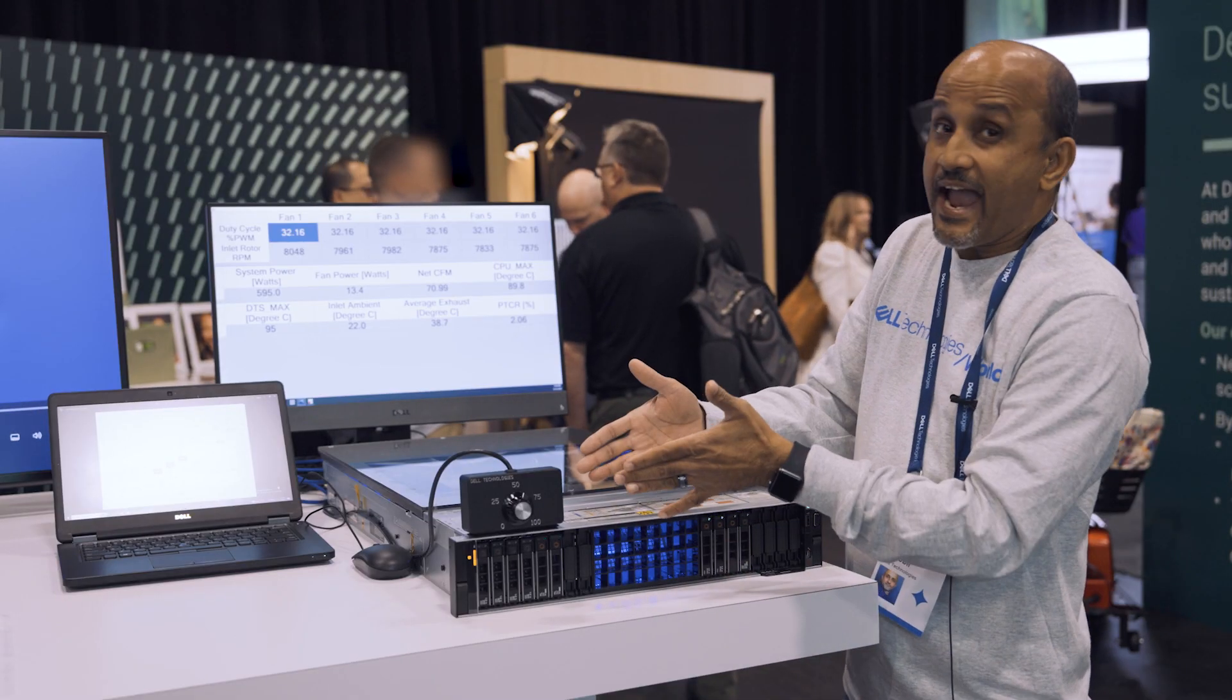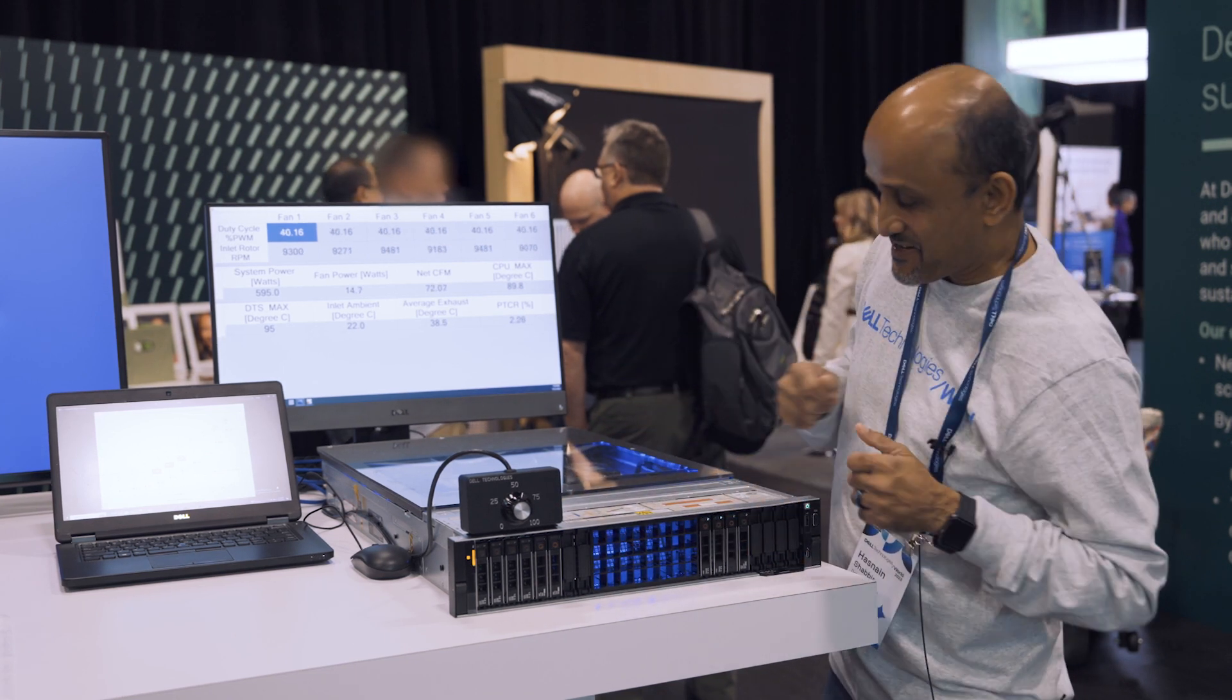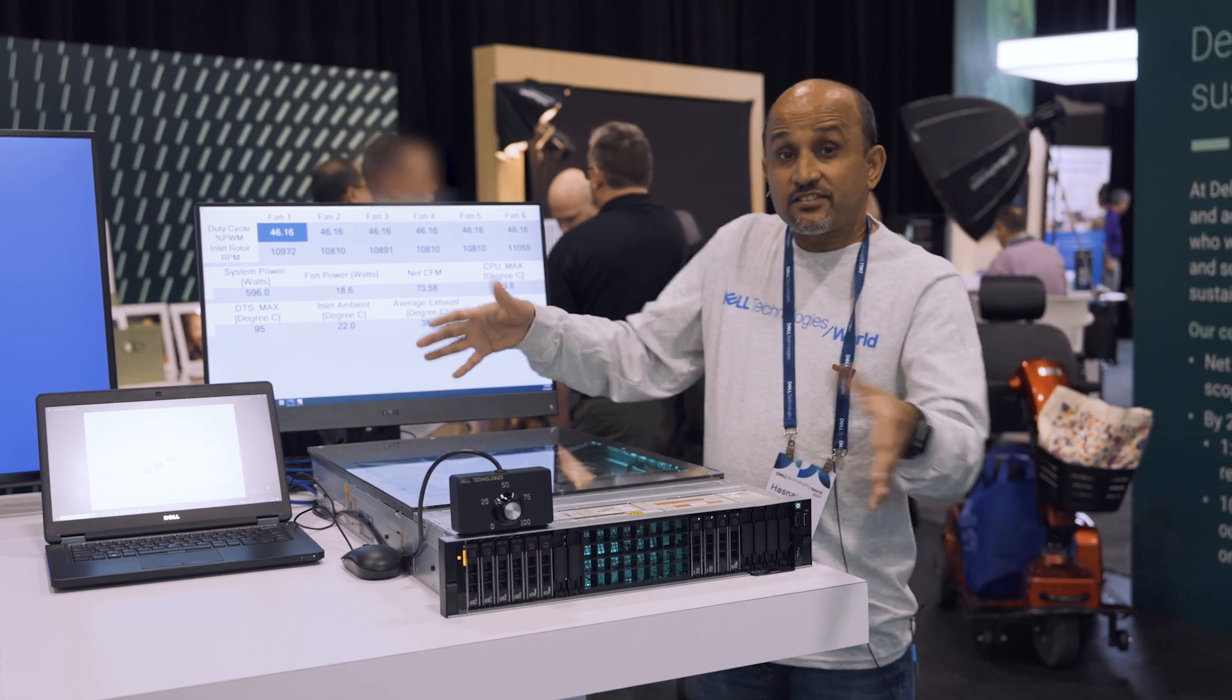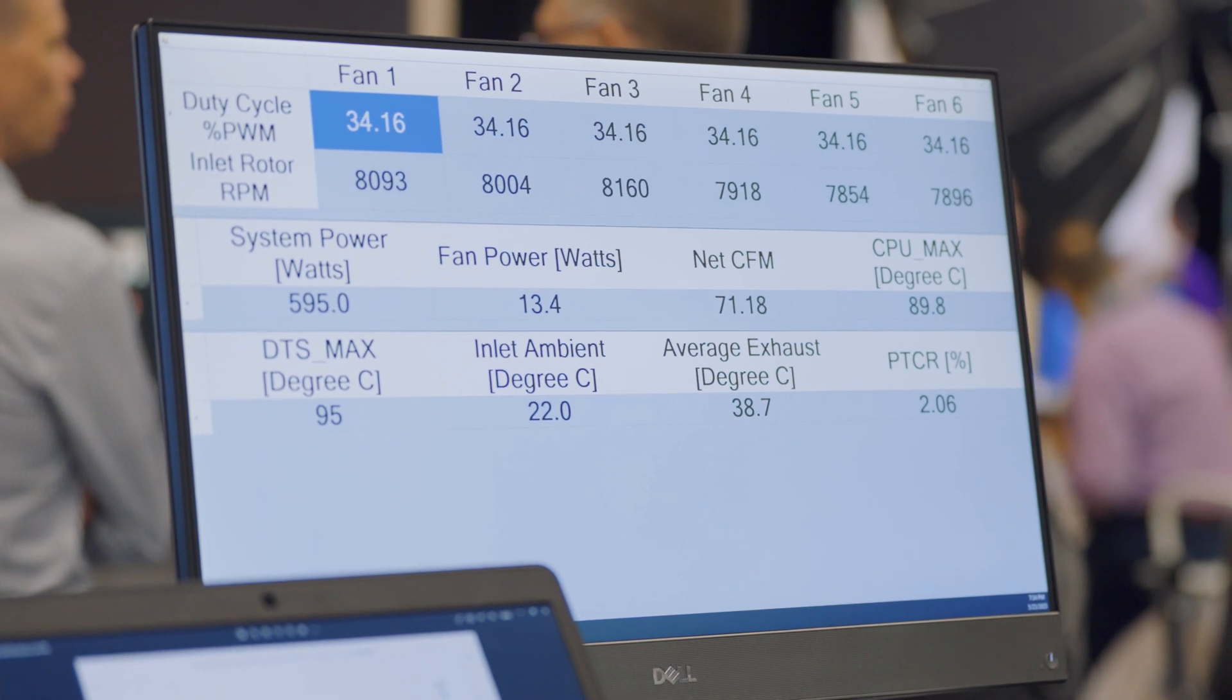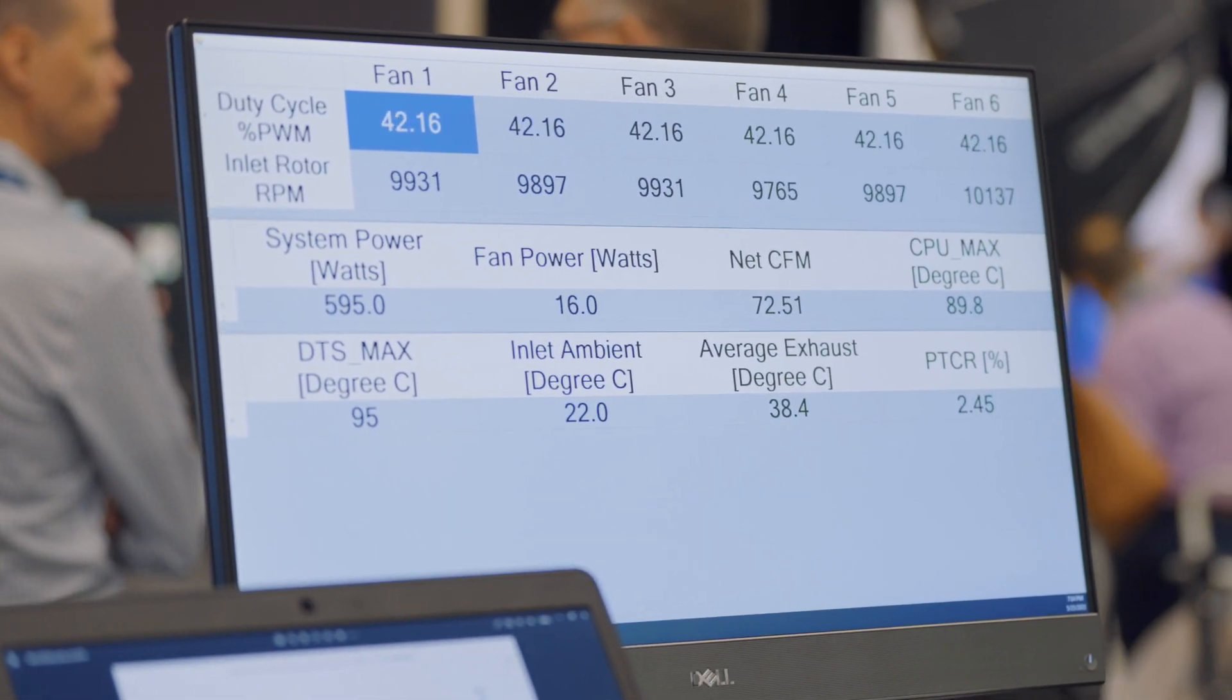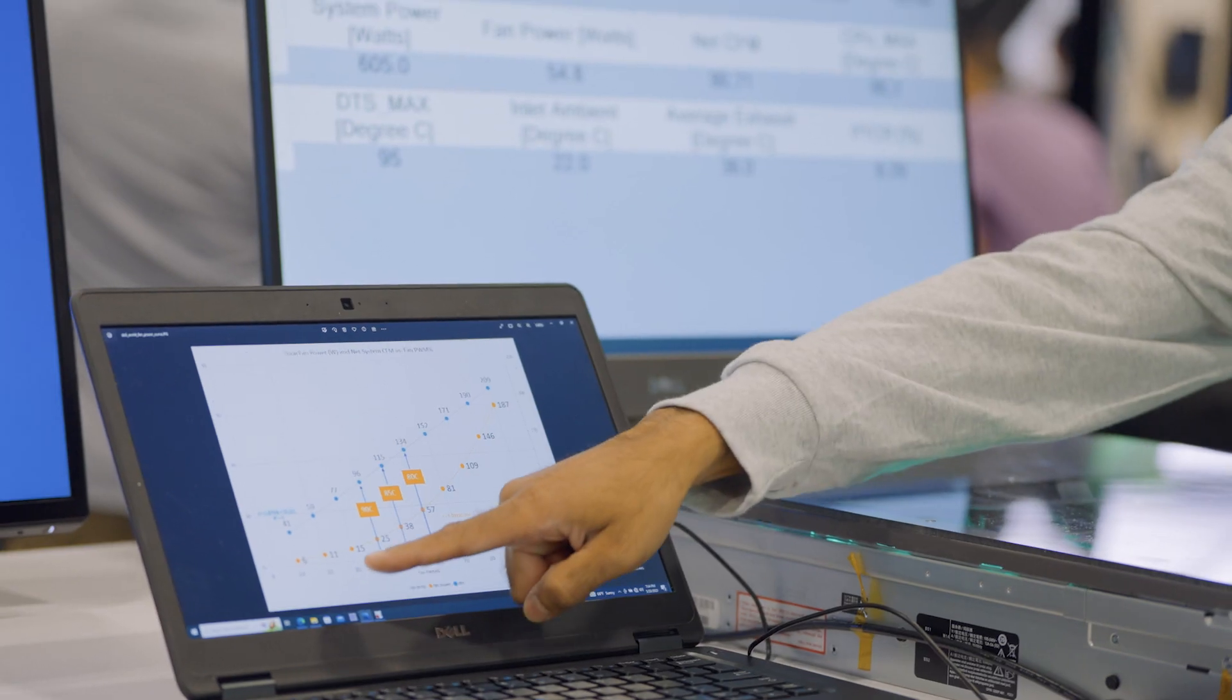This is a hack, it's not available on a real system. The idea is, let's say this is a white box not optimized from a fan control perspective. You can see the fan speeds are going up. We were operating around 25 percent before at 13 watts, and now the fan power is moving on this curve.